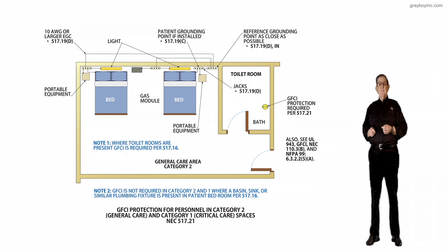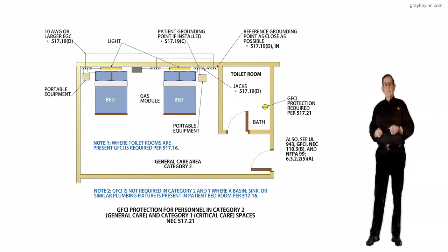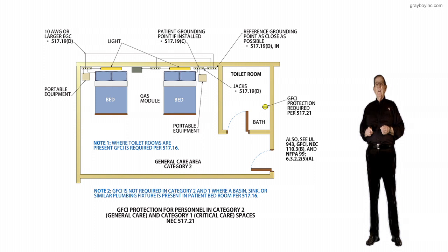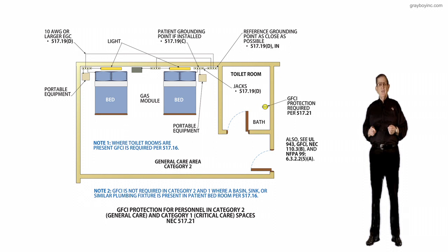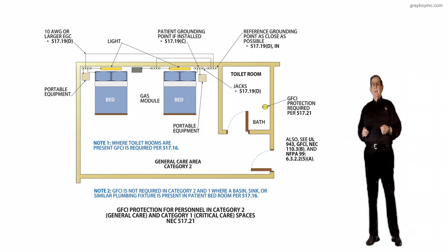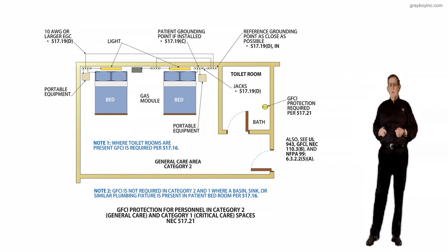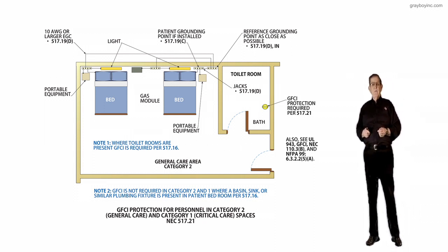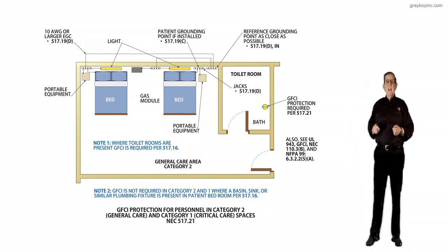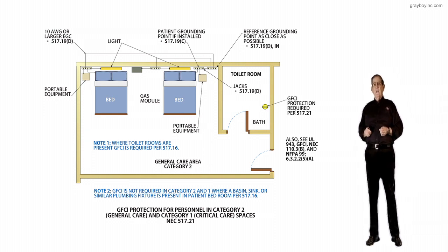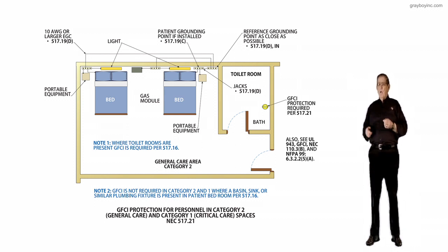Now, the purpose of a change, of revision has been accepted. And this revision to this section has made it very clear to clarify and differentiate the GFCI protection requirements for patient bed locations equipped with sinks or basins, and the GFCI protection requirements for patient bathrooms and toilet rooms beyond the patient bed location, but still within the overall patient room.